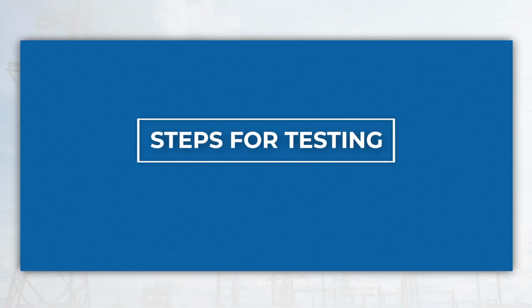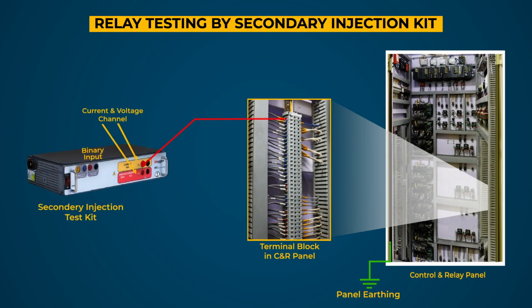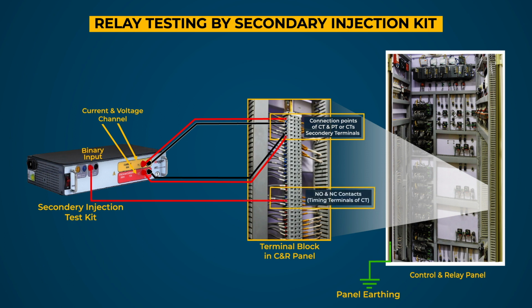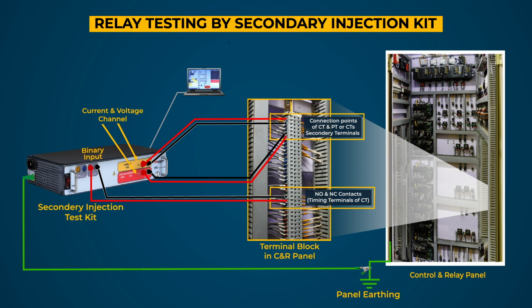Steps for testing. First, connect the current or voltage channels to the terminals of CT and PT or CT's secondary on TB of relay under test. Connect the timing terminals of relay under test to the binary input of test kit. Make a connection of earth terminal of test kit to the equipment earthing. Connect the test kit to the laptop installed with compatible software for testing by Ethernet connectivity. Connect the single-phase 230-volt power supply to the test kit and switch on the power.